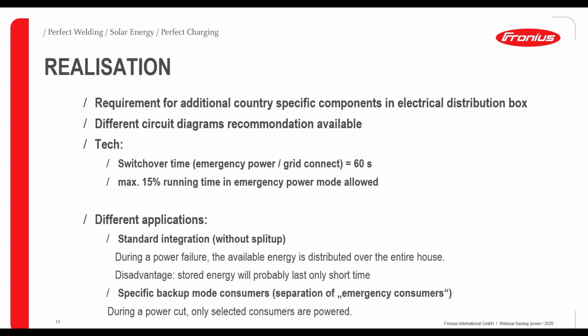Yes, then we have different applications, so also take care about a split-up of the loads in a house. It can be an advantage if you split up the loads, because some very high power loads, for example an EV charging station or a heat pump with high power, can discharge the battery in maybe an hour or so, and then the customer has no more energy for the other important loads in the house, which is maybe a refrigerator or some lights or whatever. So take care, ask the customer what loads he has got in his house. Is there anything which is maybe not needed in a blackout situation? Then it would be good to split up the loads.